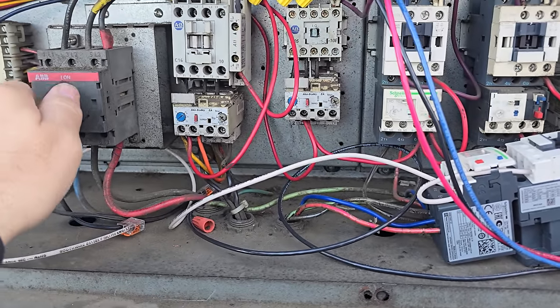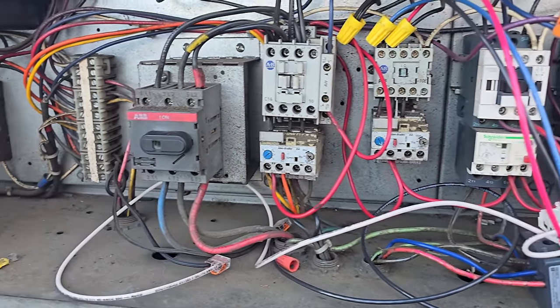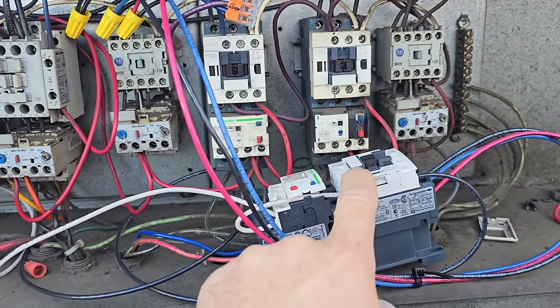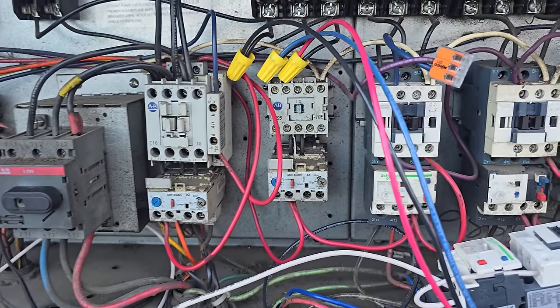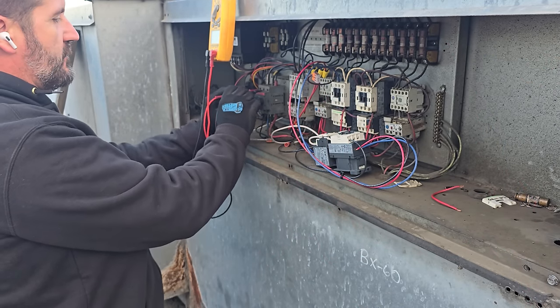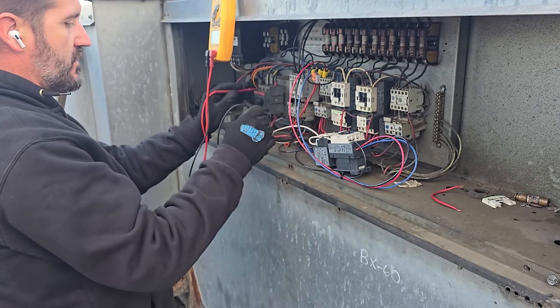So we're gonna turn this system off. All the exhaust fans just shut down, makeup air shut down. We're gonna get this temporary starter pulled out. We're gonna get this one replaced, and then we're gonna fix a few other issues. All right, we're gonna verify that we've lost power completely.